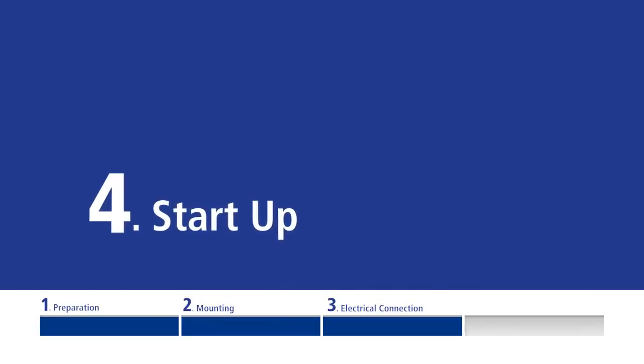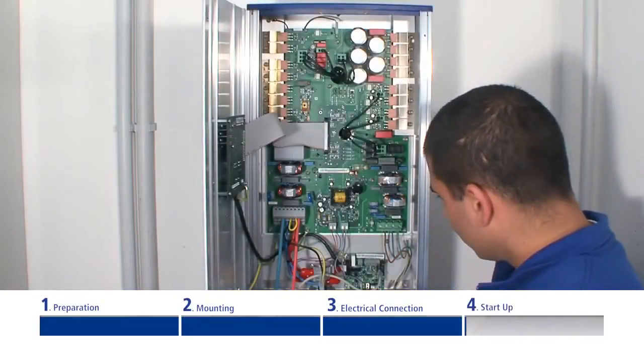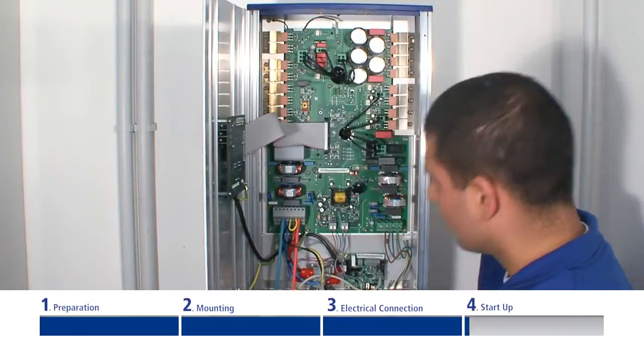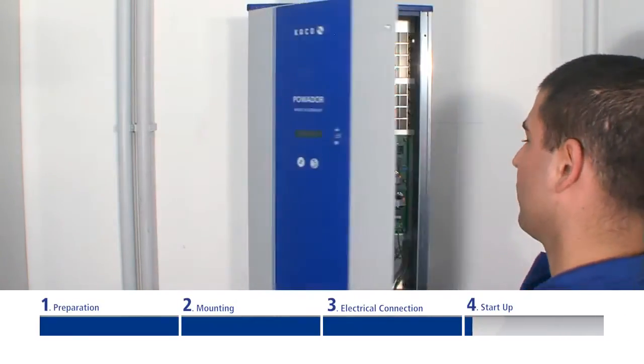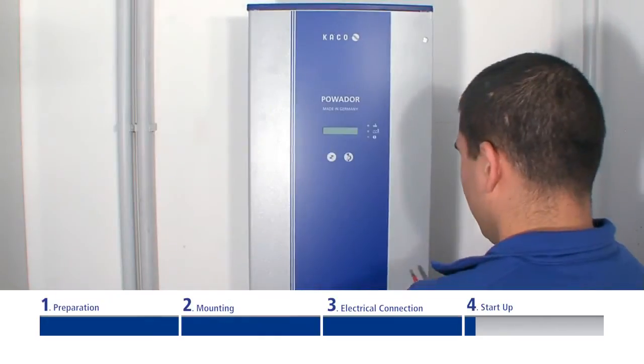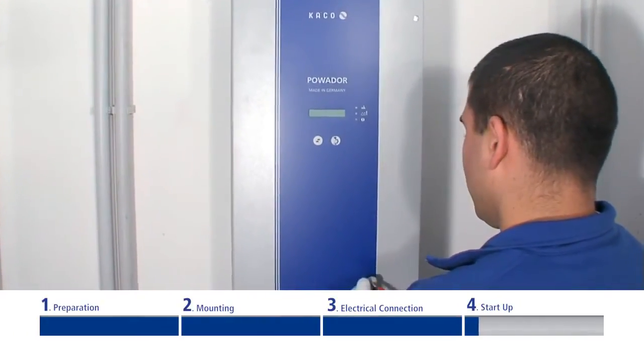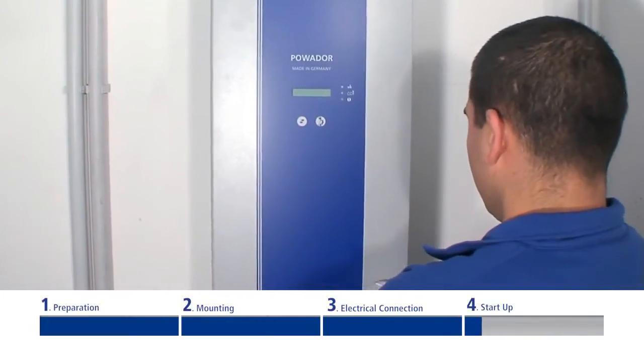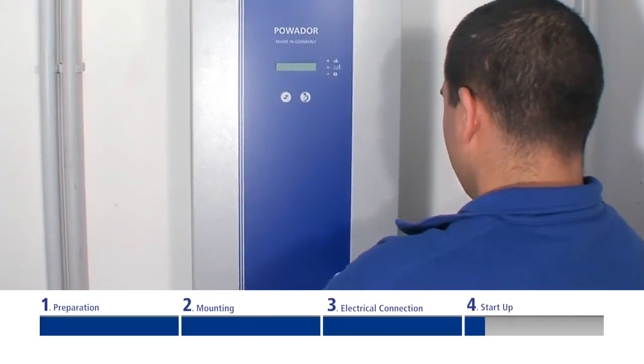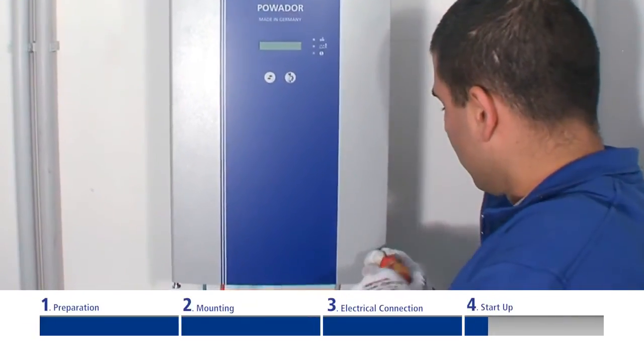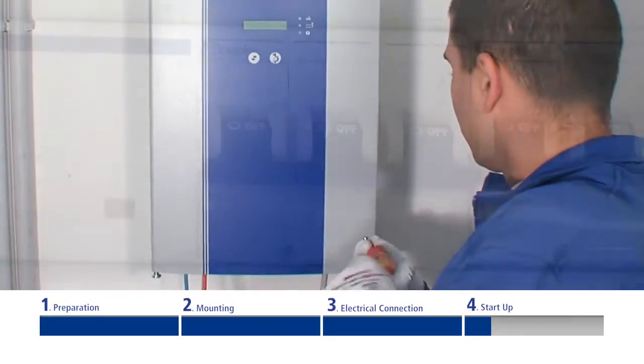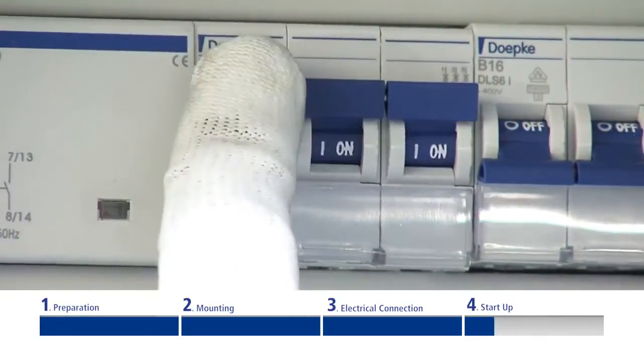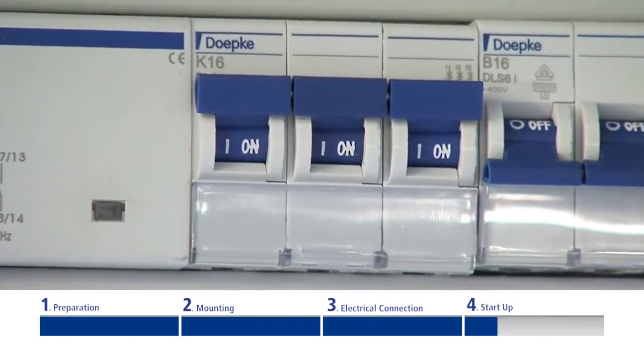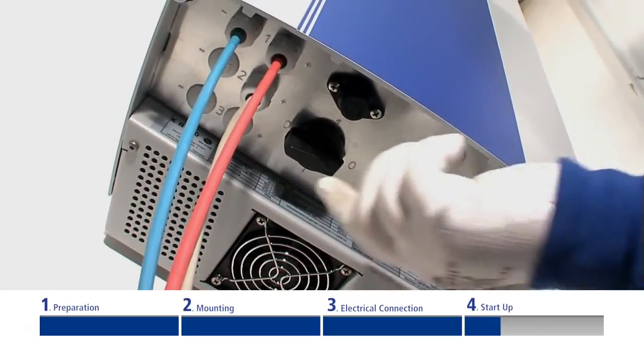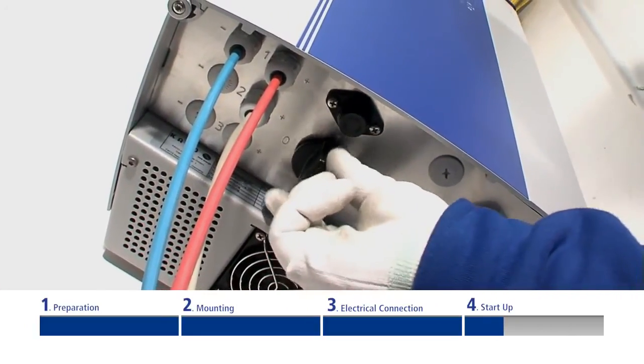Startup. Now the inverter is mechanically and electrically installed. The inverter can only be put into operation under daylight conditions when the solar generator is energized. Close the housing and secure the door with the 2 screws. Switch on the line voltage via the external circuit breakers. Afterwards, reconnect the solar generator via the DC disconnector.